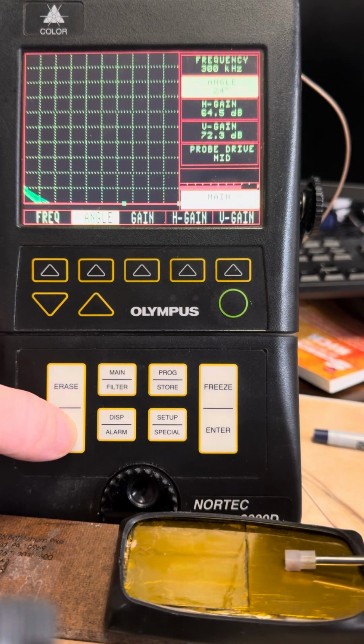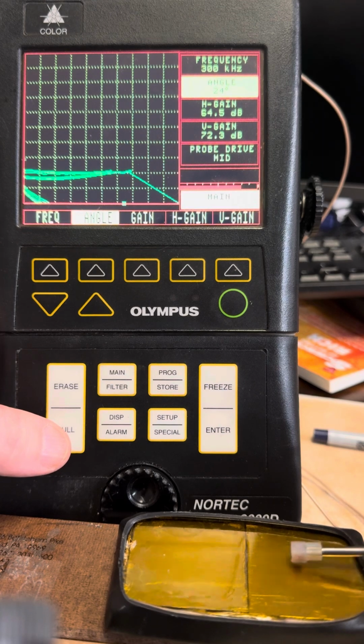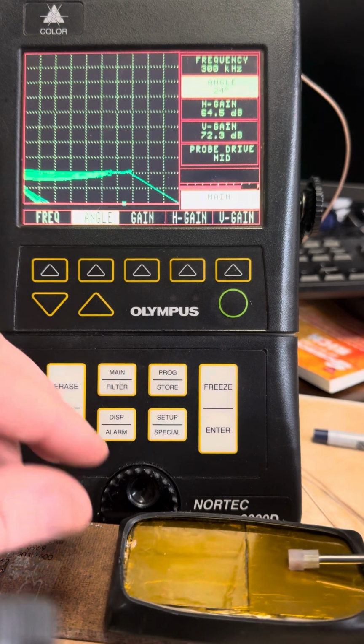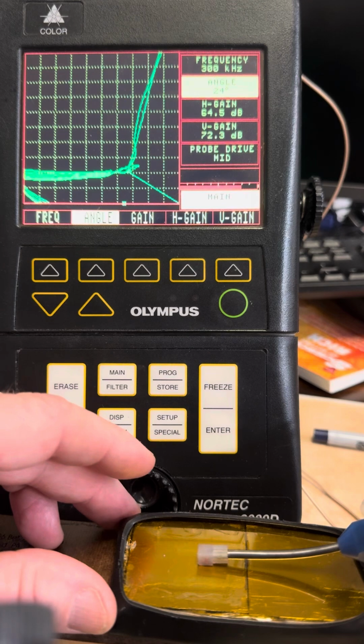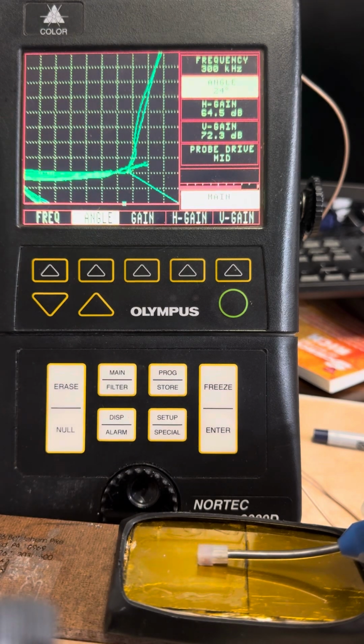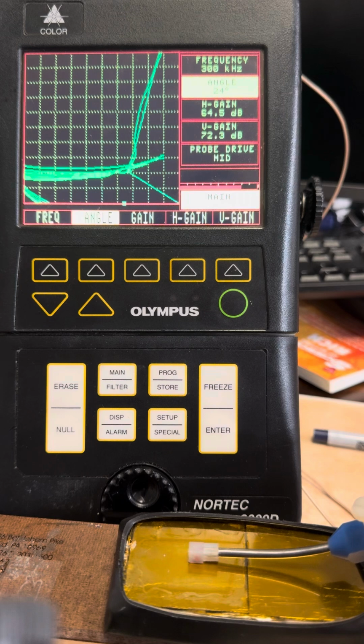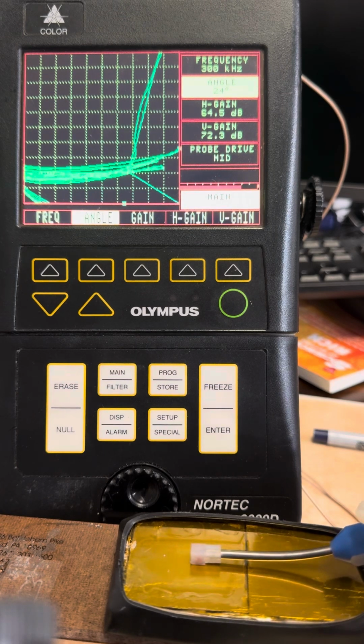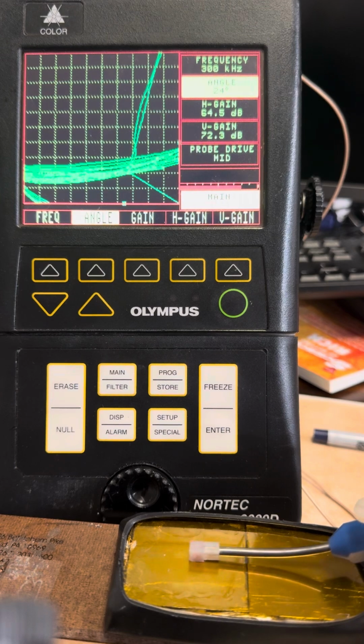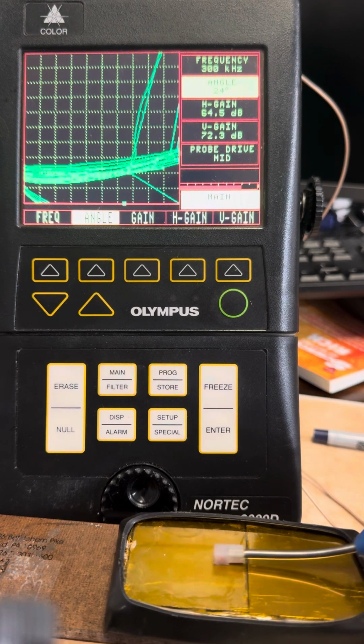So when you calibrate using this block, again, you always want to null on your material. And you want to make sure your noise is horizontal. You want to set that to full screen height, and that should give you decent sensitivity for your smaller cracks. But remember, you always have to null on the material, so you can set your amplitude and your angle on this block to set it up roughly.